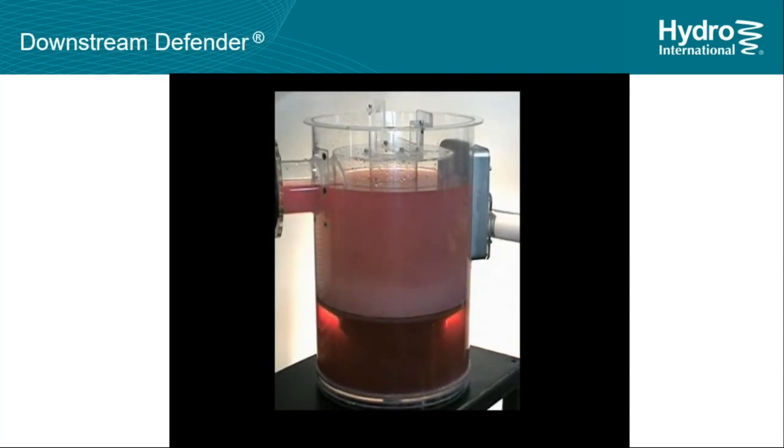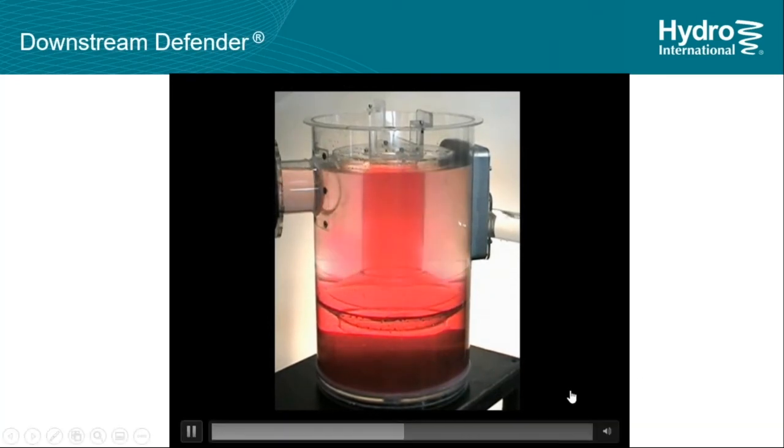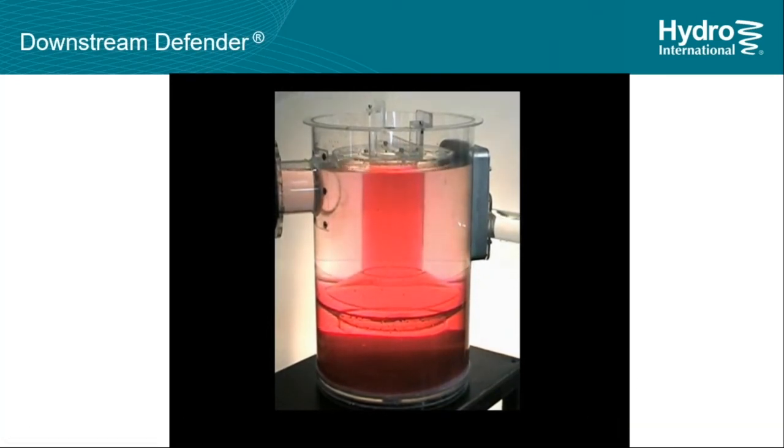And then what our internals do in that internal connection to the outlet pipe is that increases the amount of time that water spends inside our system. So right there you can see our goal is for the 80% removal to happen right there in that system and as quick as possible in the smallest footprint as possible. At the 30-second mark, you saw it ramped up to a peak flow. So that first 30 seconds was the water quality flow, followed by the peak flow for the device.